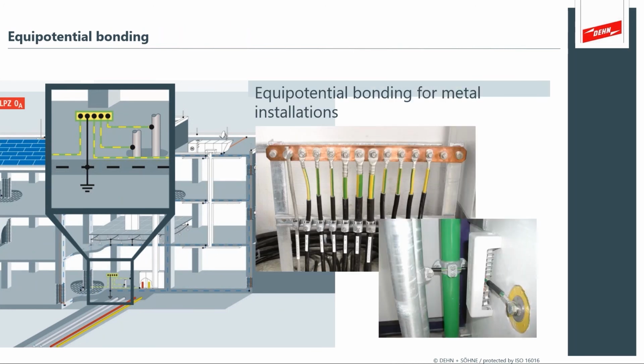And you'll see a lot of structures that look just like this, where we've got that master bar, and then all of the main grounding features of the building will come to this master ground bar. That way you have a single point of earthing that's exposed that you now connect all of your electrical systems to. So you'll see this very commonly at your home. This would look like the National Electric Code Article 250 earth bar going into the soil, and then you'll have an earth bar within your electrical service panel. At larger facilities, this would appear as a dedicated master ground bar. And that's what's important about an illustration like this, is that you see it's the single point of contact for all that earthing.